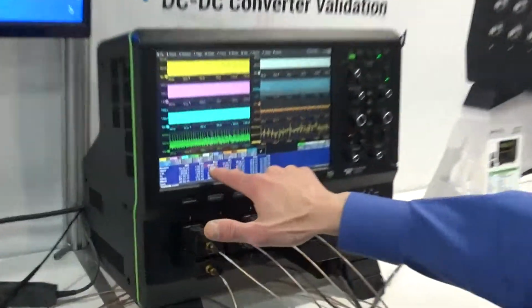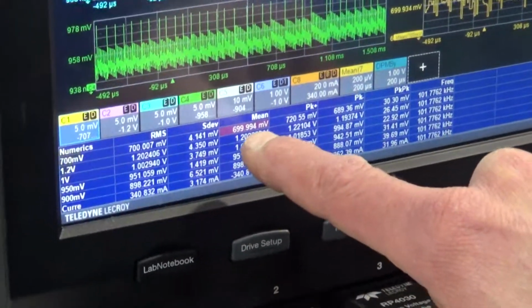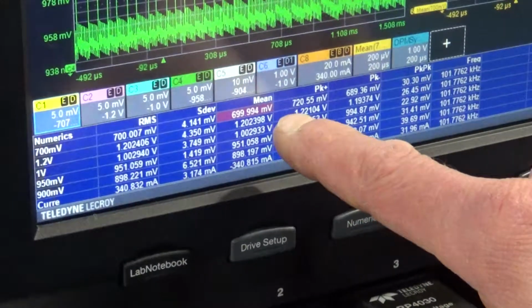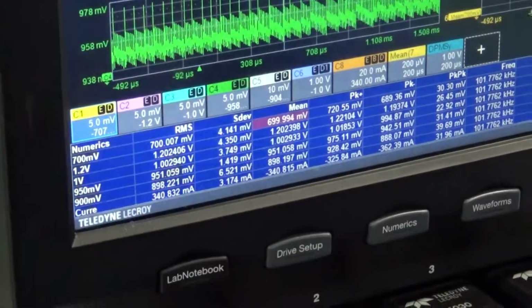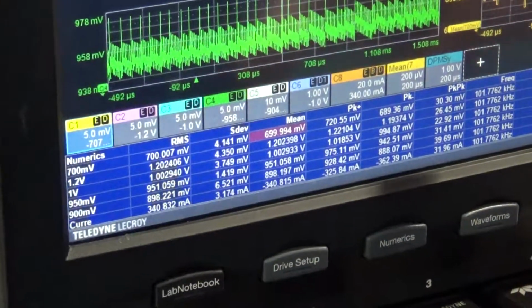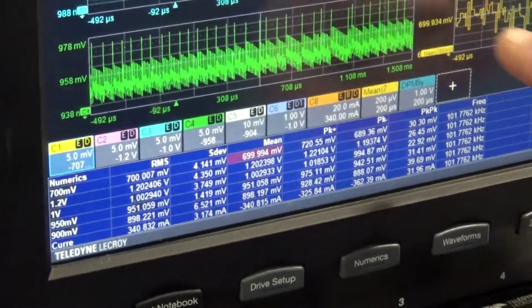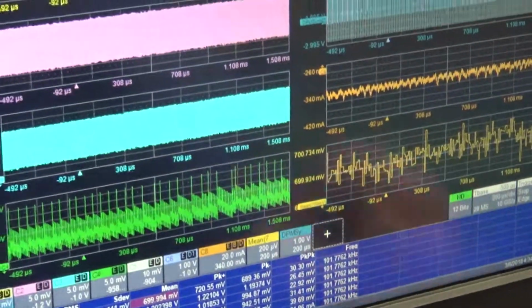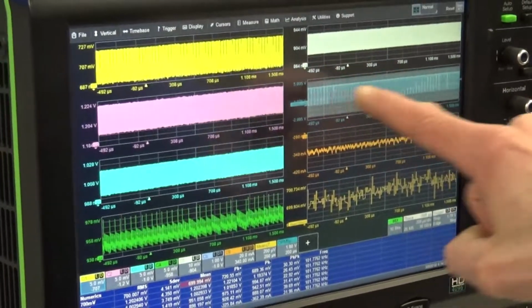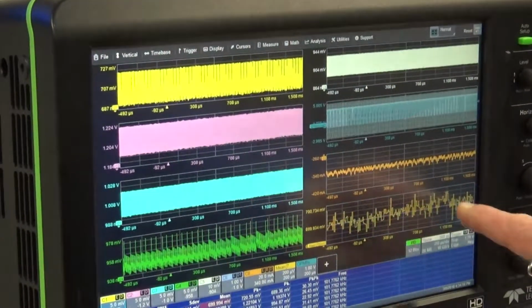If I touch that there, you see that's purple. That's the 699.994 mean value for the 700 millivolt rail, as I expect, but there is some variation of that rail over time, and we plot that variation over all those individual per-period measurements right here. So that is not a captured waveform, that is a calculated waveform that helps bring out the behavior of something that's changing, but it's very difficult to see what the change is without this type of program.